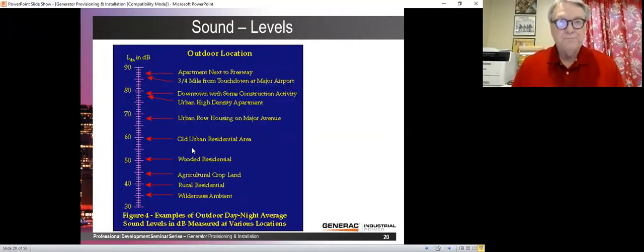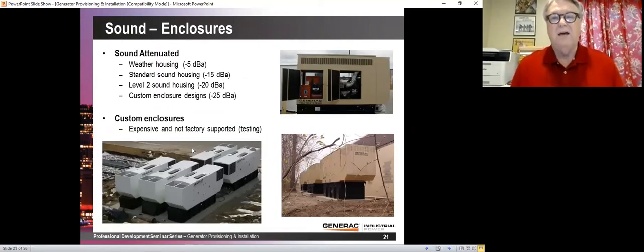Sound levels. This shows typical sound levels on a generator, and what you want to do is get a sound level on the entire generator. Now here are some sound attenuated enclosures. Sound level is measured on a flat asphalt surface 23 feet from the generator. Why do they do that?